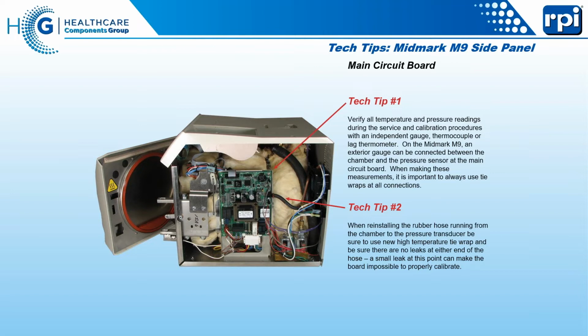Also, while we're here talking about this piece of tubing, it's really important. It connects the chamber to the pressure transducer, and it has tie wraps at either end. There's a bit of copper and a fitting, with tie wraps at both ends of that tubing. If those tie wraps fail or loosen up, you'll get a lot of spurious error codes, pressure codes that don't make sense, temperature codes that really shouldn't be like that. You need those tie wraps in place, and they need to be specialized tie wraps.